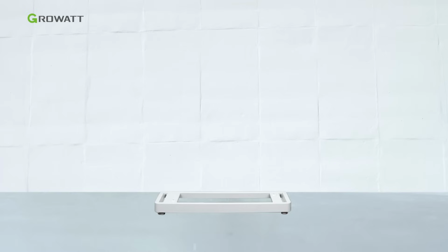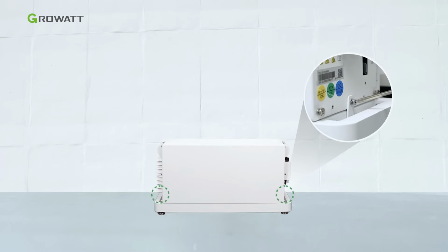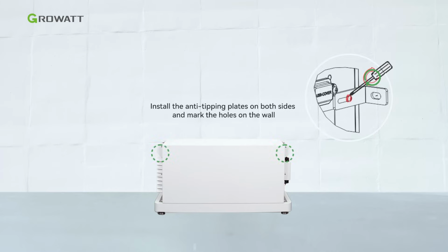Position the base in the appropriate location and adjust the base feet to keep them level. Pay attention to the orientation of the battery and avoid placing it in the wrong direction. Place first the battery module onto the battery base, then install the connecting pieces on both sides and securely tighten the screws. Also, install the anti-tipping plates on both sides and mark the holes on the wall.